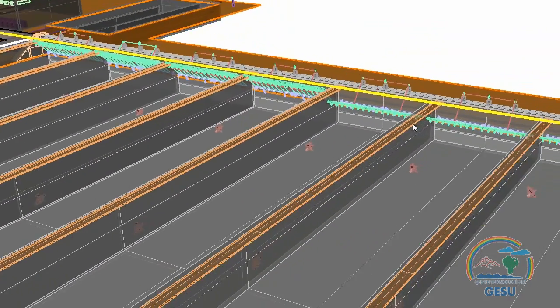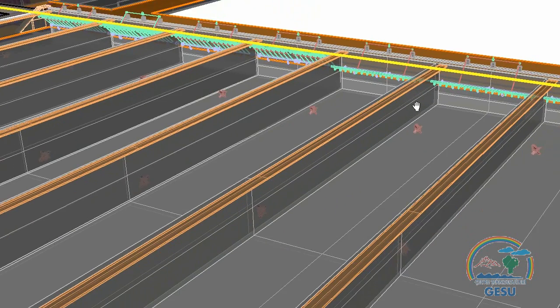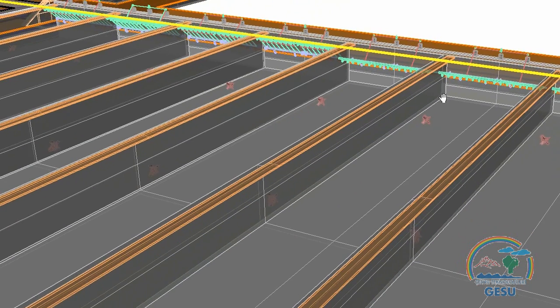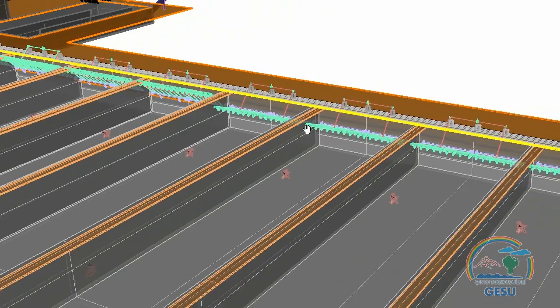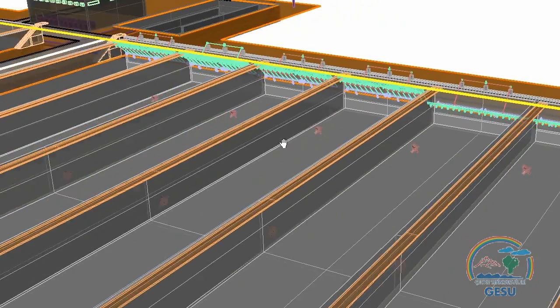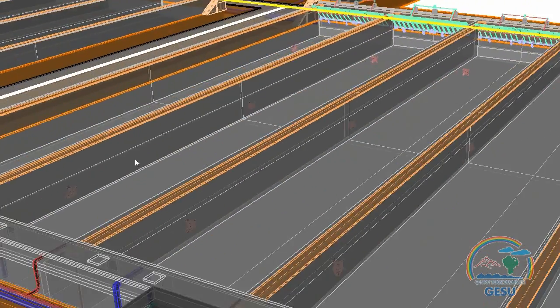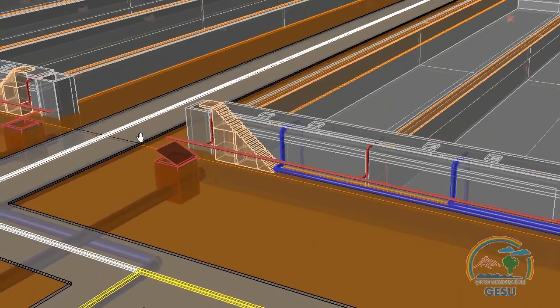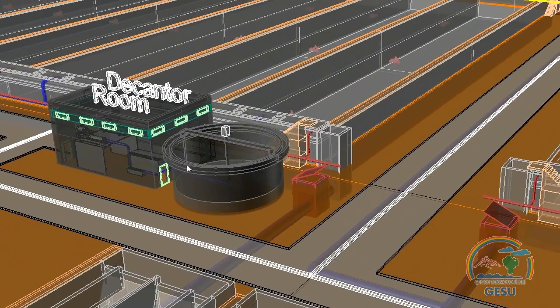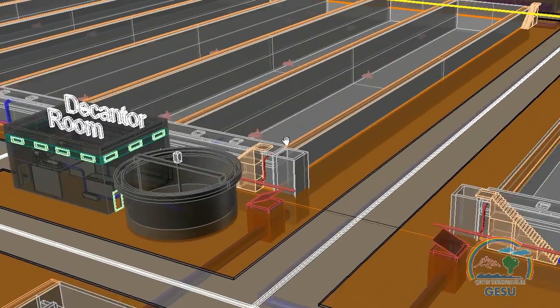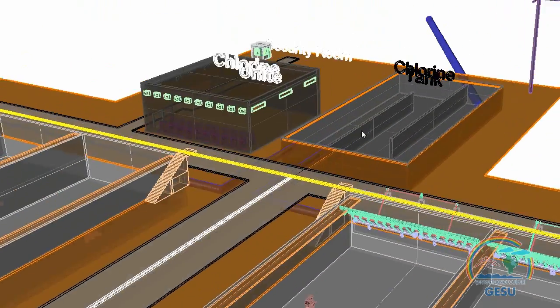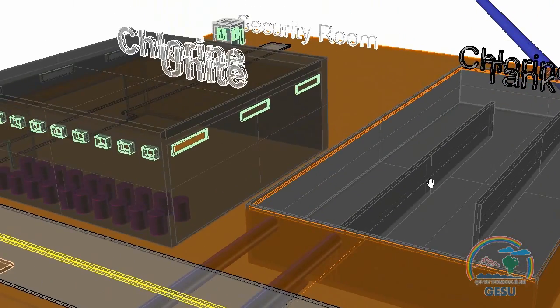The SBR reactors work with a fill, react, and decant strategy. Each fill-react-decant period is called a cycle. Filling time is 1 hour for each reactor. When one reactor is filled, the pen stocks are closed and the next tank starts to fill.